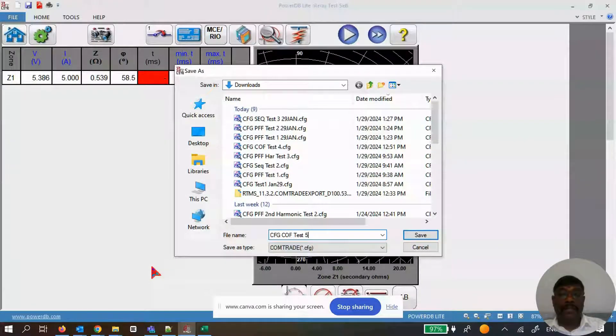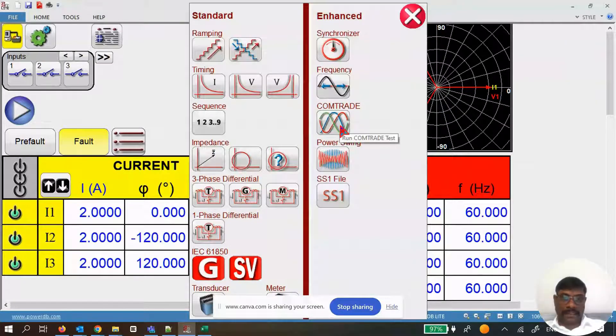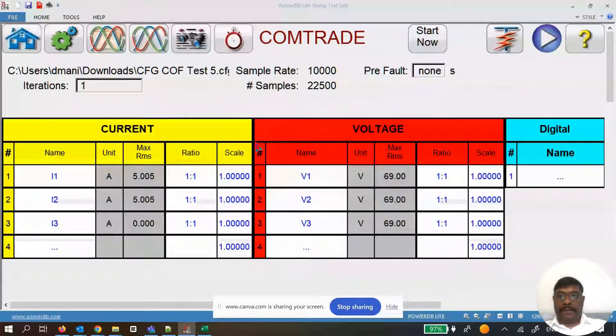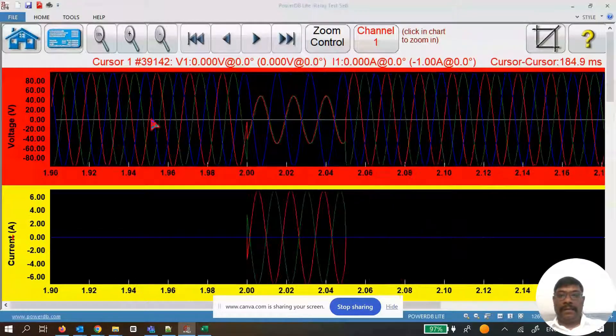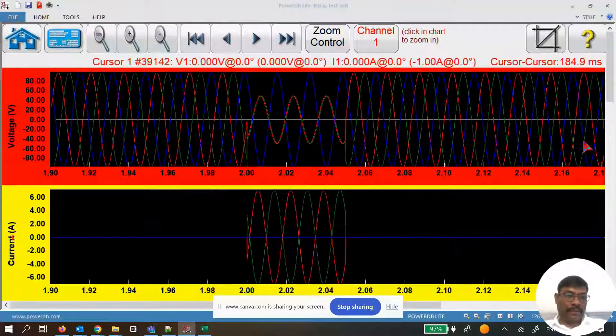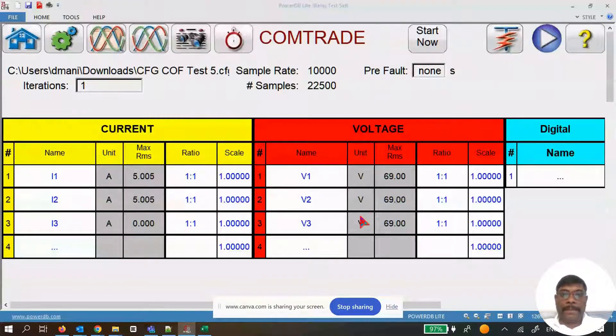Once the test runs, click the Export Comtrade icon, name it 'CFG COF Test 5', and export. Then go to the home screen, select the tools list, click Comtrade, use 'Open Comtrade File', open the CFG COF Test 5 file, and go to waveform view. You can see the pre-fault injected as three phase and the fault as an AB fault at 180 degrees. The post-fault portion corresponds to the post-fault setting in the timer configuration screen, which is approximately 200 milliseconds. Once exported, you can import and play the file normally.